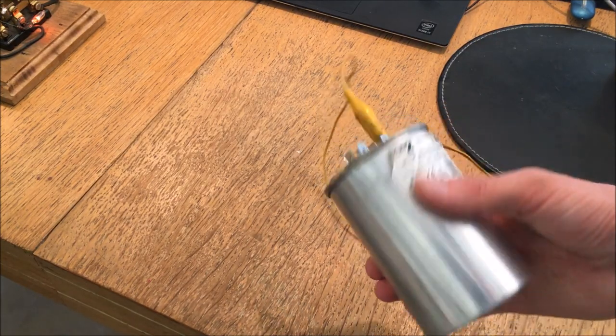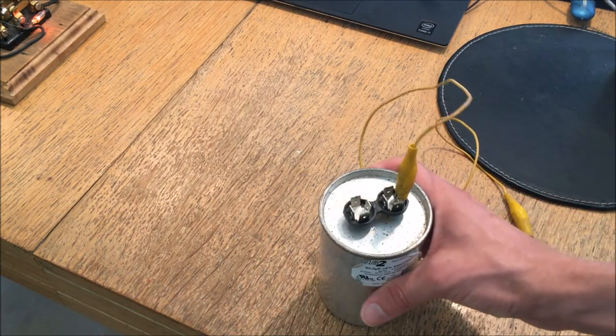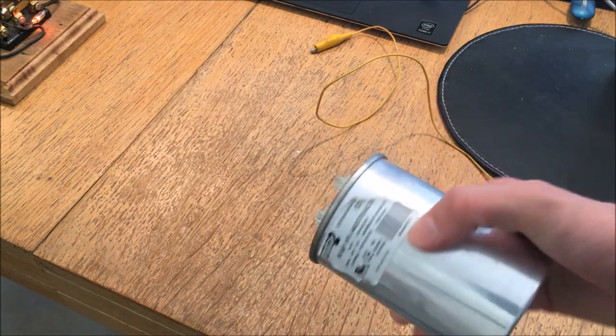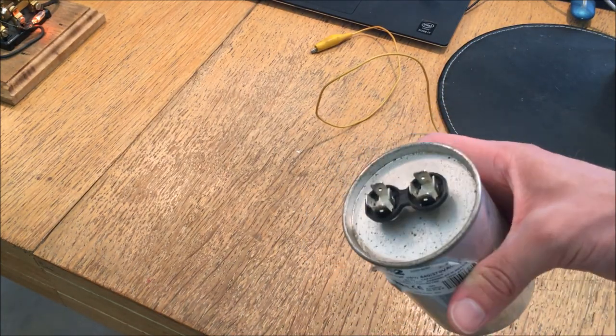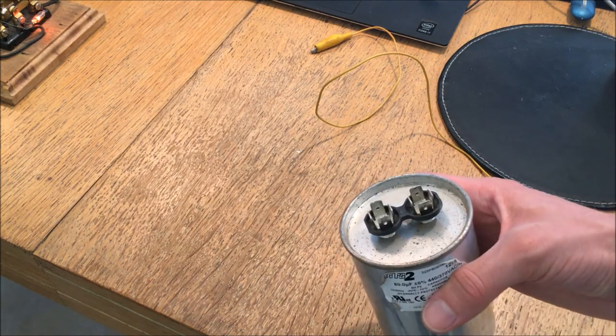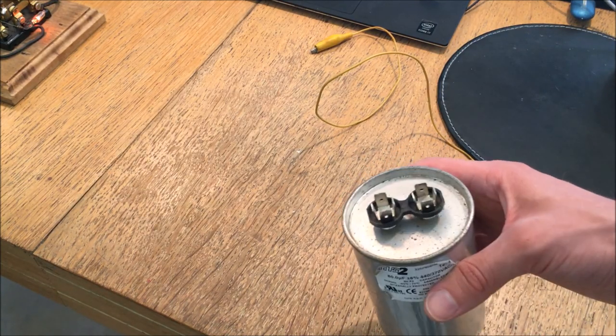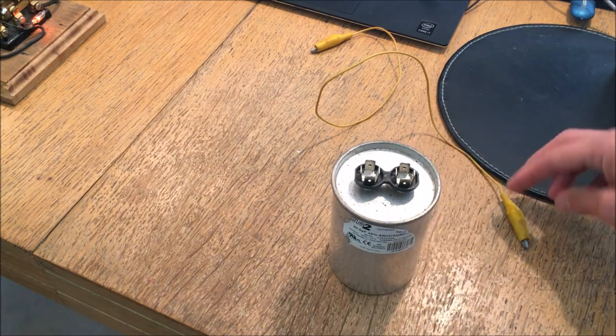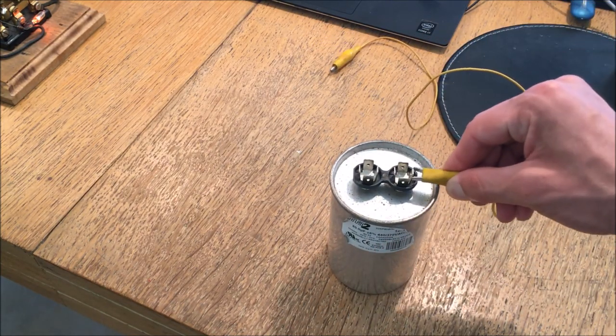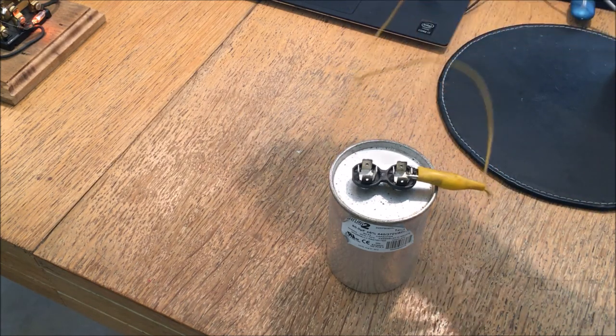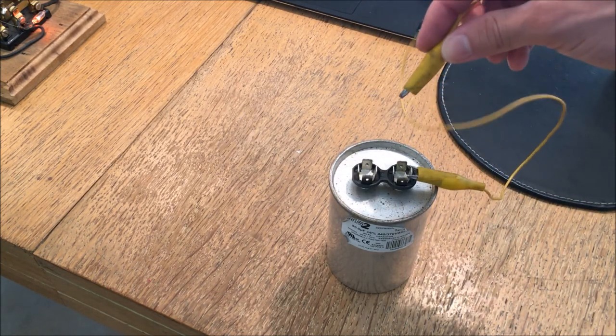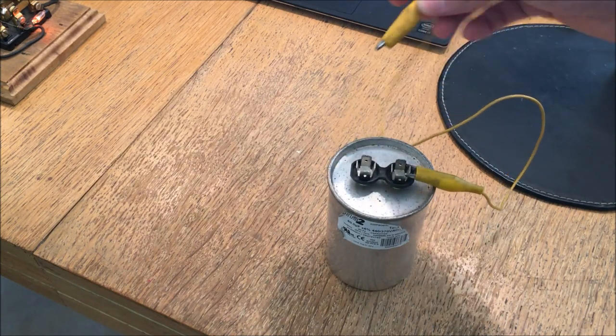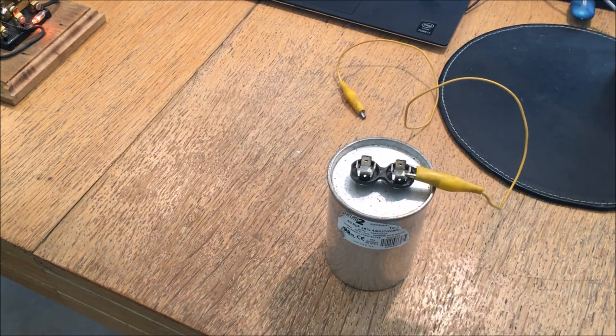This capacitor looks fairly innocuous right? I mean you could take this wire off, it looks like it's just been sitting around in your closet, you have no way of knowing if there was any real hazard with it. It would be easy to assume that this is fairly non-hazardous since it's just been sitting around. In reality however this capacitor is still holding 160 volts from where I charged it and it can deliver potentially hundreds of amps for a split second. That's a pretty big bang you got there.